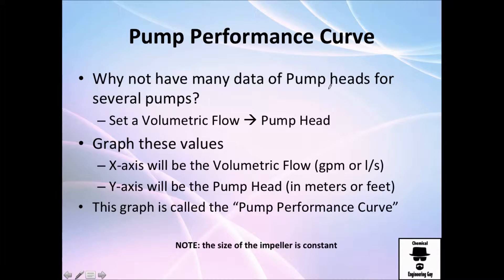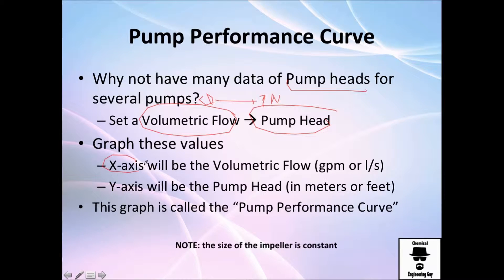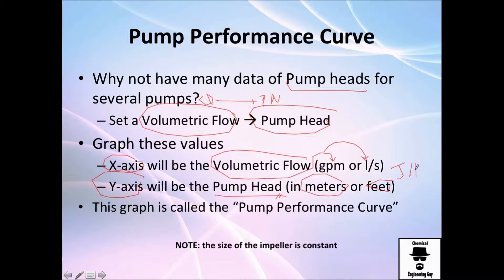Imagine we could have many pump heads for many flow rates — given Q, we will get many heads. We're going to graph the x-axis as our volumetric flow rate, which is normally measured in gallons per minute or liters per second, and on the y-axis we'll have our pump head, typically measured in meters or feet, even though this might be joules per kilogram. Once we calculate all the flow rates and pump heads, we call this the pump performance curve.